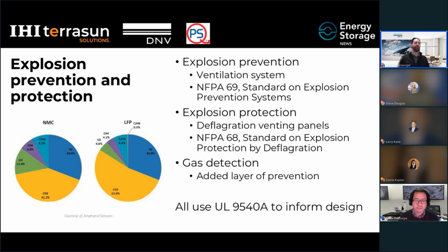A lot of design work goes into designing the HVAC and cooling systems for the batteries, so we have a good idea of the airflow within the container in an air-cooled environment. We use data from the cell-level tests to see how these explosive gases move within the container and to evaluate whether gas concentrations ever reach above the lower flammability limit, where there could be an explosion risk.